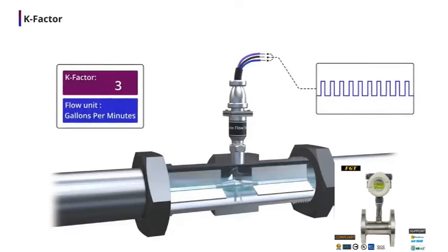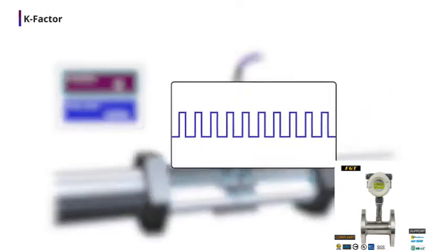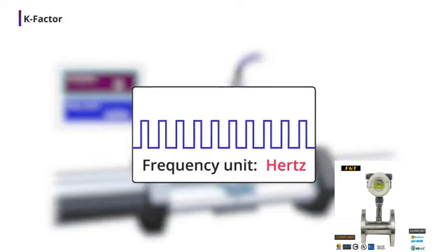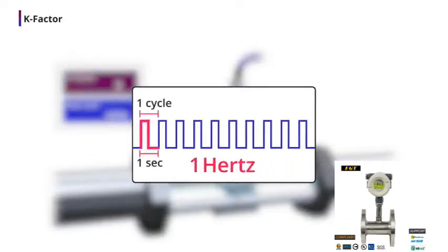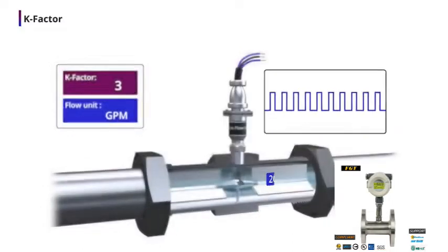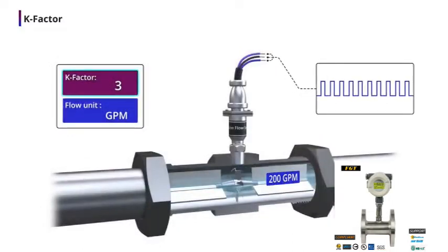Let's assume we are using a turbine flow meter to measure flow in gallons per minute, or GPM. This turbine flow meter has a K factor of 3 pulses per gallon. Recall that the unit for frequency measurement is hertz. 1 hertz is equal to 1 cycle per second. With that in mind, we say that the turbine flow meter produces a frequency of pulses per second, which we express as hertz. If we have a K factor of 3 pulses per gallon, the output frequency at a volumetric flow rate of 200 gallons per minute, or GPM, is 10 hertz, or 10 pulses per second.